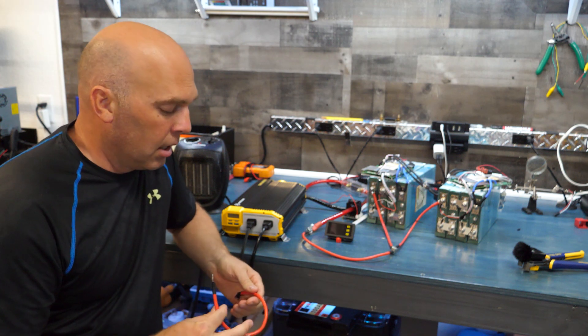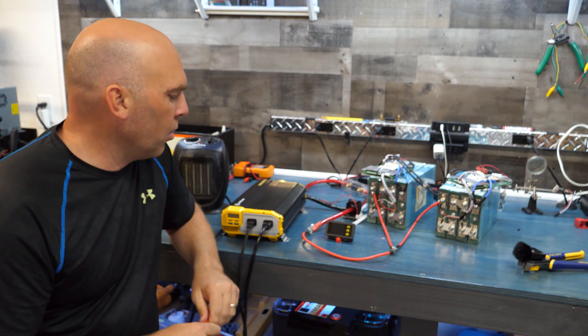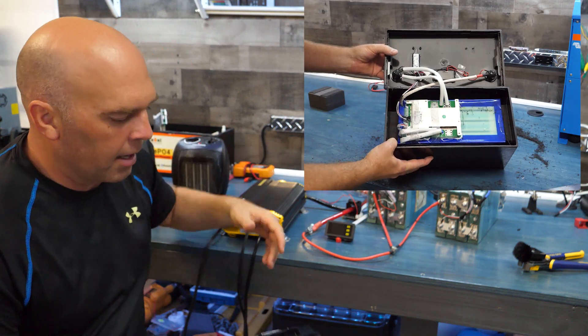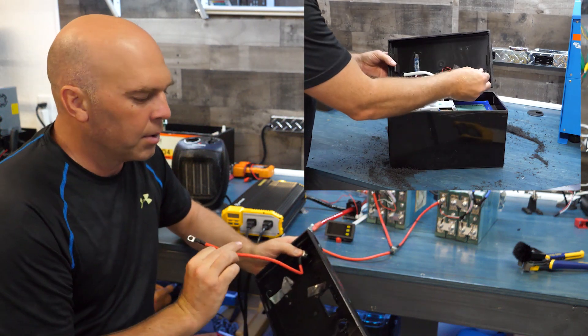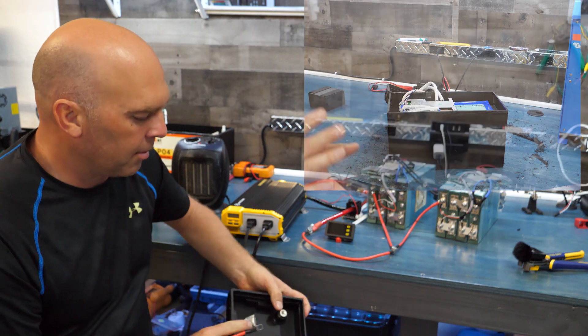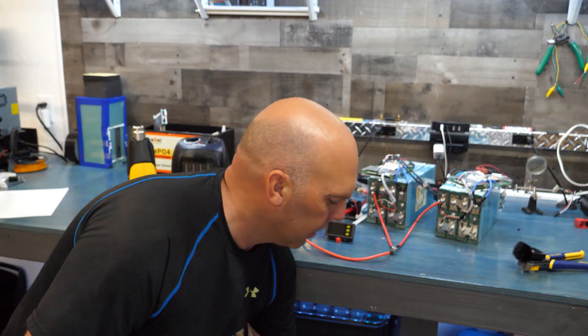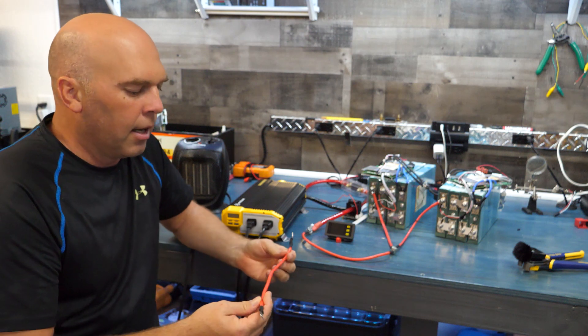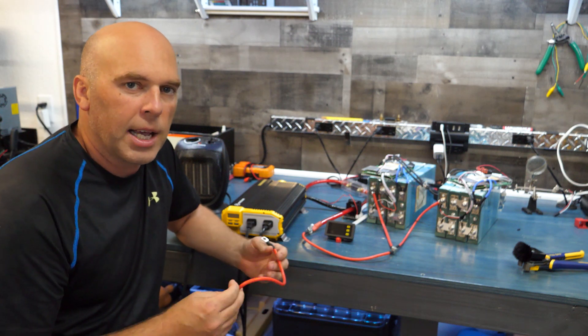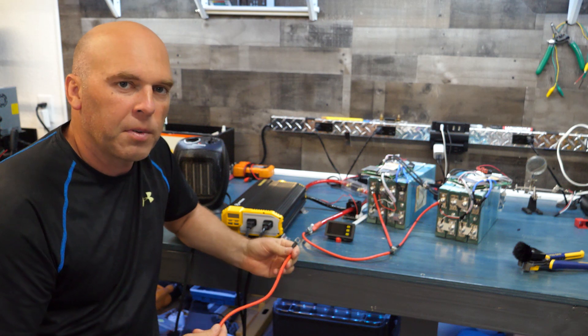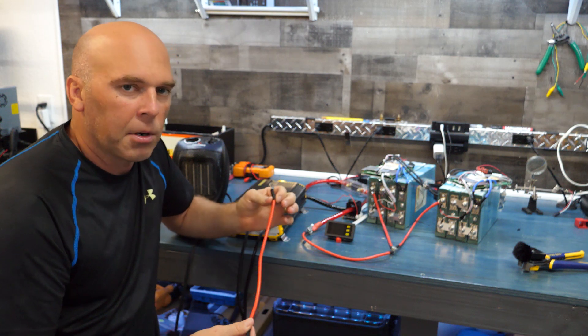So first of all, the backstory. We were cutting open that battery back there and pulling one of these two units out of that battery and on the back side we had connected to the terminal post an 8 AWG silicone wrapped wire. I made the comment on there that some people may question pulling 100 amps across an 8 AWG wire because typically the PVC jacketed versions of these cables are only rated for about 50 amps.